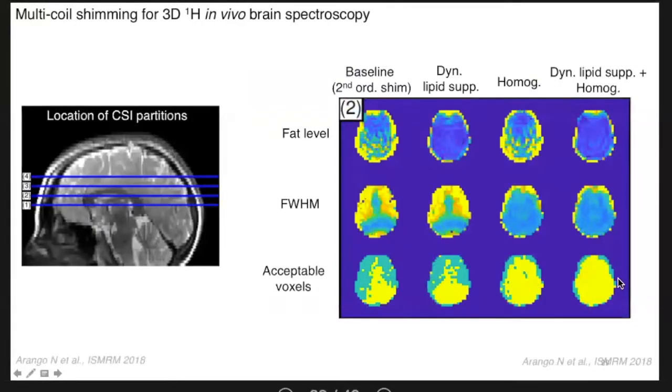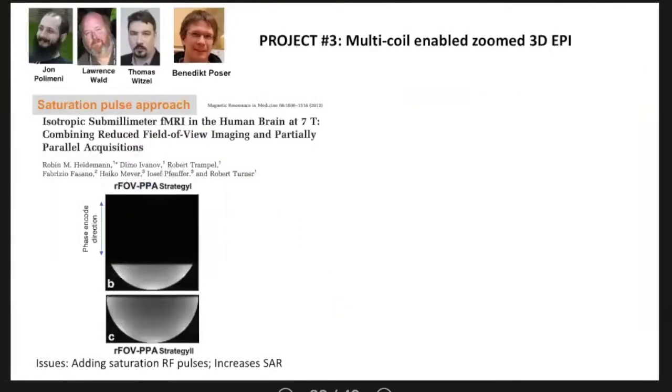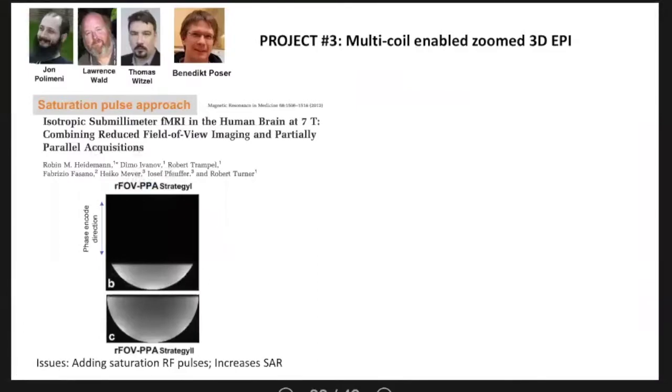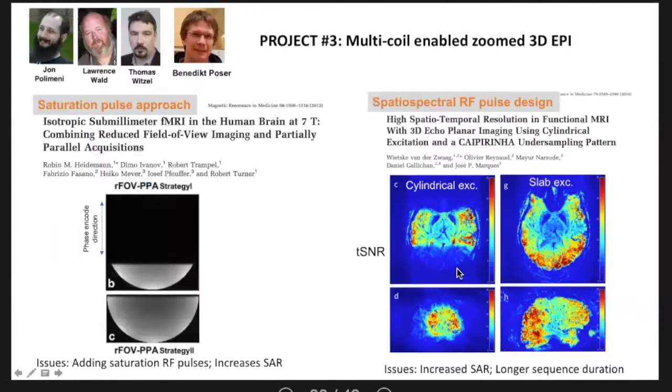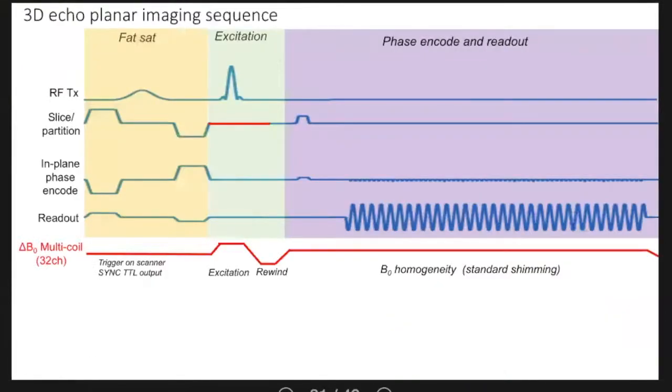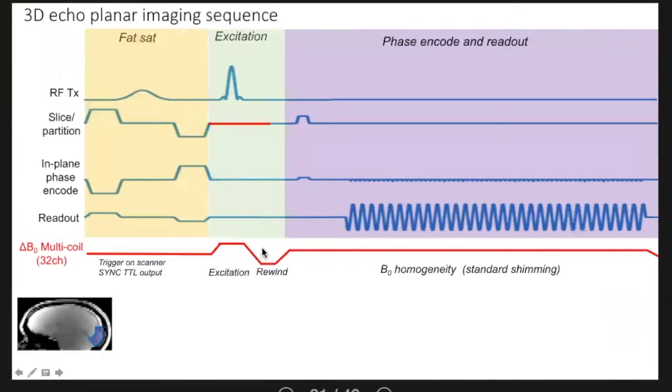And then, actually, I was talking with Jon Polimeni at a conference in Minnesota, and we realized we can use the multi-coil for zoomed EPI. And the reason you might want to zoom is that when you only image part of the field of view, you have less spatial encoding burden. So you can potentially image at the same resolution faster or image with a higher resolution in equivalent time, because you need to encode fewer k-space points. So people have done this in the past with saturation pulses or spatial spectral RF pulses, but these both bring SAR penalties. They add to the length of the sequence. They're not perfect for every application, especially at 7T, where SAR is bad. So we modified a 3D echo planar imaging sequence. We turned off the conventional slab select gradient during the RF excitation pulse, and instead, we played out pulses on all 32 of our multi-coil AC-DC coils.